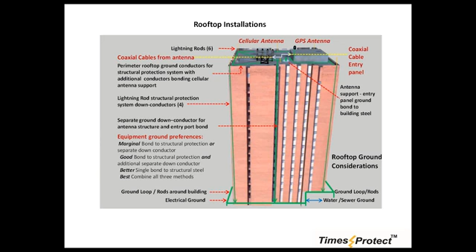There was also a question about using the cold water pipe. Yes, if you're certain there are no plastic pieces interconnecting the copper, or that plastic won't be added later due to modifications of the cold water pipes, it's always good to have redundancy. A cold water pipe is good as long as it's totally metallic and in very conductive surroundings. But in addition, I'd advise running an additional redundant ground system, just in case somebody has to cut a piece of broken metal pipe and fit it with PVC.